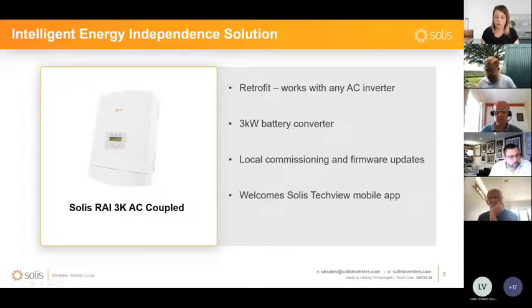And the second, which has also been extremely popular on the UK market, is our solution for retrofitting installations which already have a PV inverter on site, and for customers who want to add additional storage capabilities to their systems. This inverter will be installed, connected near the PV inverter, and it will work as a way to maximize self-use, to store energy into the batteries when there is an excess of energy that is normally exported into the grid, and to discharge it when there's a need for it. So this is what the 3 kilowatt does.